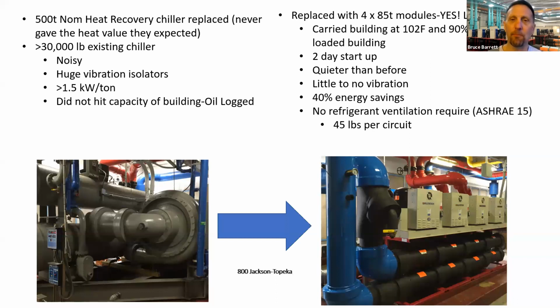A lot less capacity. How were we able to do that? Well, we did the calculation of capacity on the hottest day of the year. You do that by taking your delta T, your flow, and divide by 24. Delta T times GPM divided by 24. And the math said that we needed 4 85-ton modules, less capacity than 500. When we did the startup, we carried the entire building with a full 10-degree delta T.